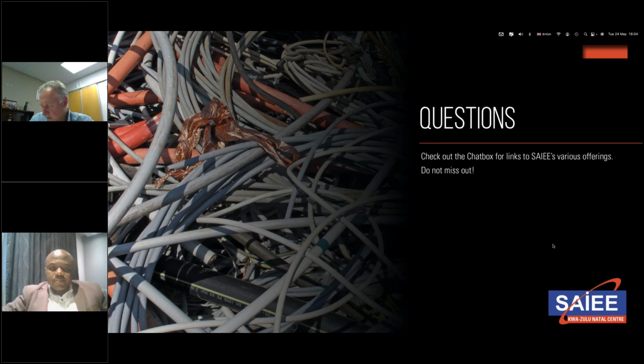Michael asked about the vibration limitations of aluminium. I think for standard 1350 aluminium, I would say don't use that material in installations where there's known to be vibrations. As I mentioned, aluminium 1350 in particular doesn't have a defined fatigue limit. So it's not as if you can say, I'm going to apply this stress to the conductor, I'm going to apply this number of vibrations and amplitudes to the conductor, and it's going to fail at a predicted level. It's not really the case with aluminium, as you might have with copper or other materials. That level is not defined.